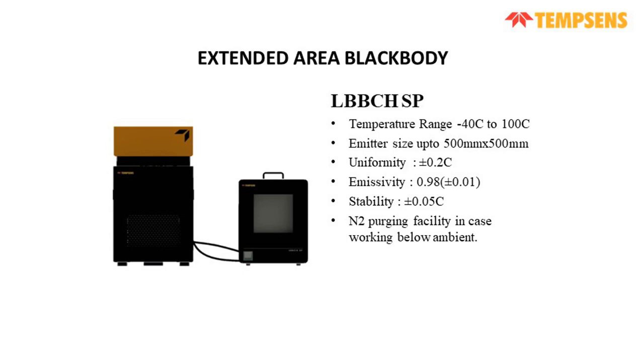The emissivity is very high, that is 0.98 with plus minus 0.01, and the stability is plus minus 0.05. At temperatures below ambient, to prevent condensation, a nitrogen purging facility is also given for the below ambient temperature range. So nitrogen purging will work as an anti-condensation chamber. So this is the model with -40 to 100 degrees centigrade.